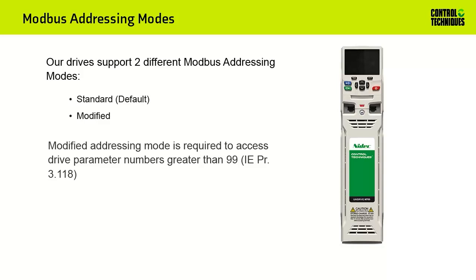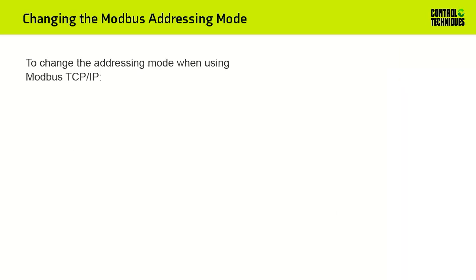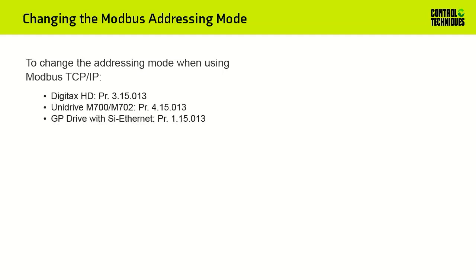For example, if I wish to access menu 3, parameter 118, I would need to change the addressing mode to Modified. For Modbus TCP-IP communication, the addressing mode is changed using parameter number 13 in the Modbus setup menu, which is menu 15. In a Digitax HD, you may access this parameter by opening slot 3, menu 15.